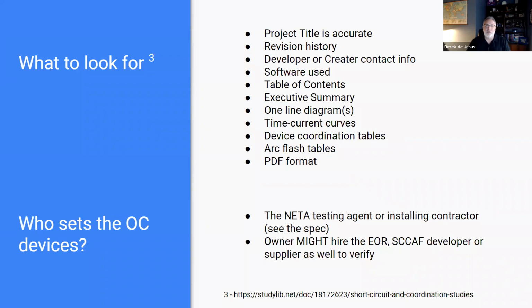So who sets those overcurrent devices? Well, this is a great mystery on some projects because a lot of times people will point fingers at one another. You will sometimes see NETA testing agents who are going to set those on behalf of the installing contractor. Sometimes the installing contractor will do it. Otherwise, the owner might hire you as the commissioning agent or bring the engineer of record out to set those devices. So if it's not very clear in the specifications, this is an opportunity for you during your design review scope to ask that question.